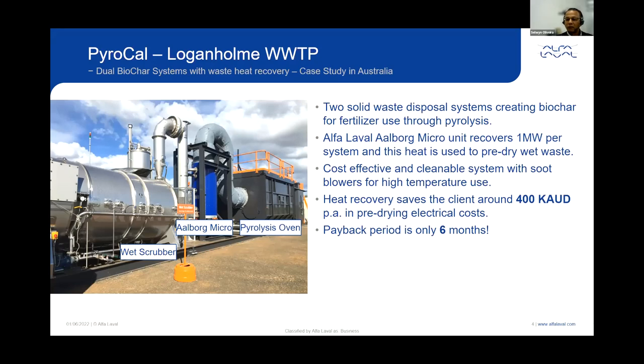The Alfa Laval waste heat recovery unit recovers 1 megawatt of waste energy from the incinerator exhaust gases and uses this to pre-dry the waste material being fed into the incinerator. This saves the client around $400,000 per annum in waste pre-drying electrical cost, which is a huge sum of money. And the system has a very short payback period of only 6 months.